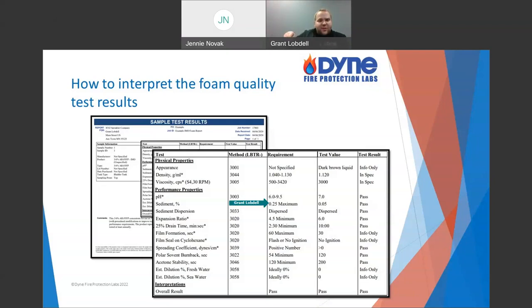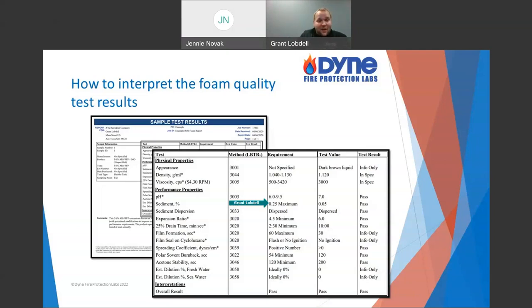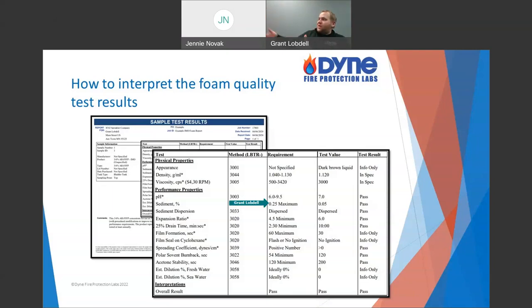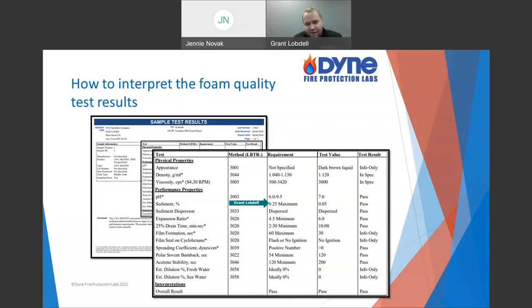If you have a rusty trim pipe with metal flakes in it and you just quickly open it up, grab your sample, and send it to the lab — you're probably going to get a bad result because that's not representative of what's in the bladder tank. If you're taking from some length of trim pipe, try to drain that out first, get into the actual tank content, and get a sample representative of the concentrate in the tank — not what's sitting in that trim pipe.